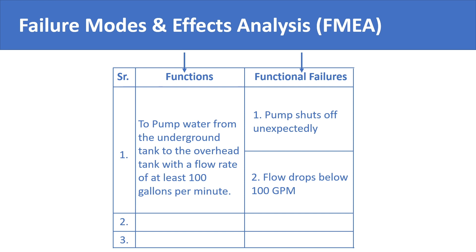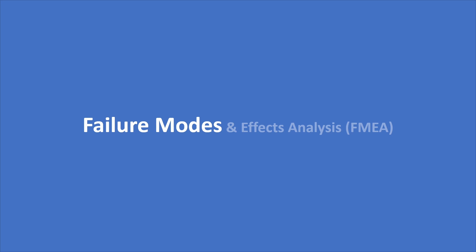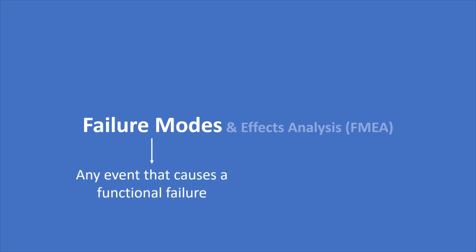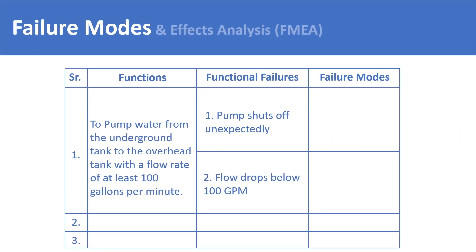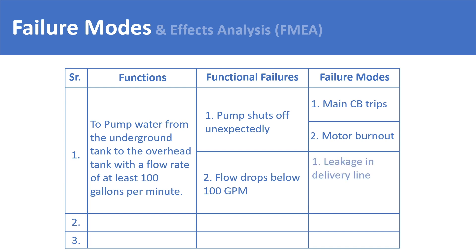The next step in the process is to list down the failure modes of each functional failure. The failure mode is any event that causes a functional failure. For example, the pump could shut off unexpectedly because of the tripping of its main circuit breaker, or due to burnout of its electric motor — both of these are failure modes. Coming to the second functional failure, the flow rate of the pump could drop below 100 gallons per minute because of a leakage in the pump's delivery line, or maybe a worn-out impeller.